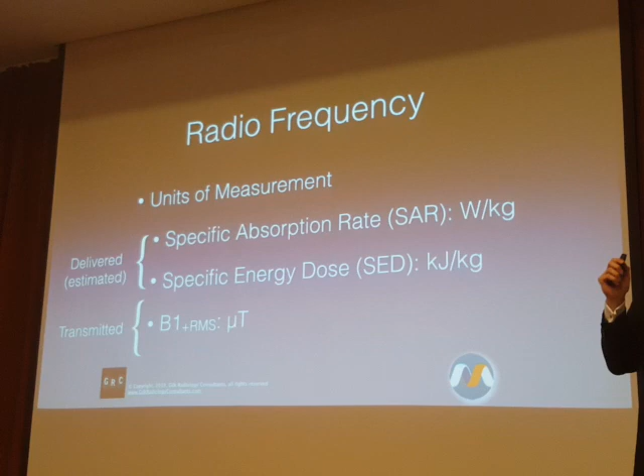But if you have a patient with an implant or device, and you have an MR system that gives you both SAR and B1 RMS, you can use whatever the more permissive value is. If the implant or device has a B1 RMS and a SAR, even if using the B1 RMS value, your MR system tells you that the SAR for that study would be above the allowable SAR on the SAR condition, as long as you comply with one or the other, you'll be fine, according to the way that the MR conditional labeling works.